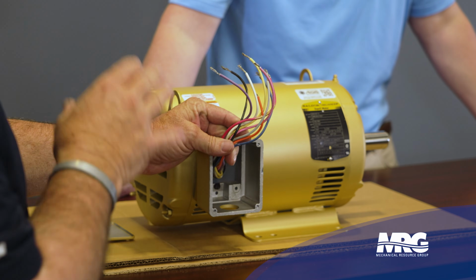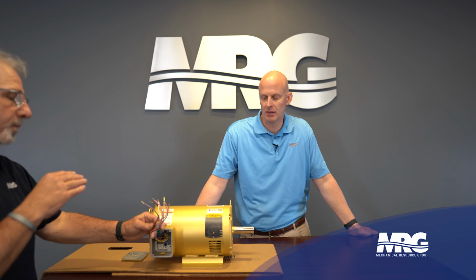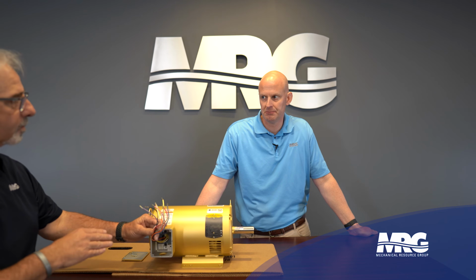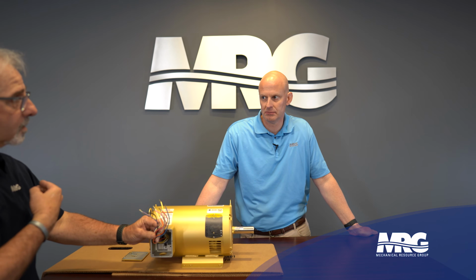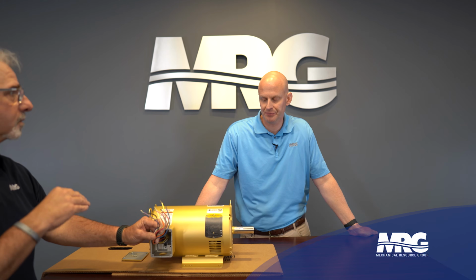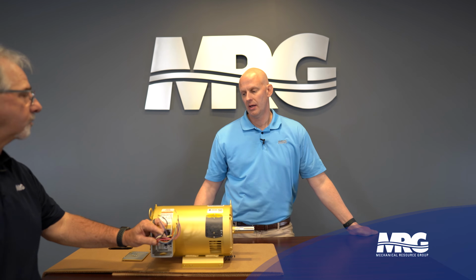Now, if your starting method is a soft start, we're going to hook this motor up across the line. If your starting method is a variable frequency drive, we're going to hook this motor up across the line, because your drive or your soft start is taking care of that reduced voltage. This particular motor is a 9-lead motor. There are some 9-lead motors by other manufacturers that are capable of reduced voltage electromechanical starting, but you really need to refer to the paperwork from the manufacturer.